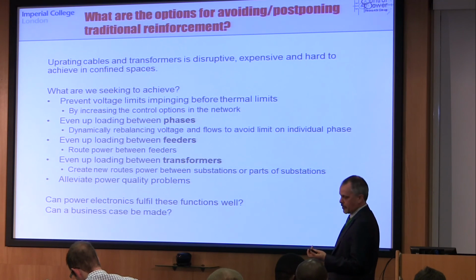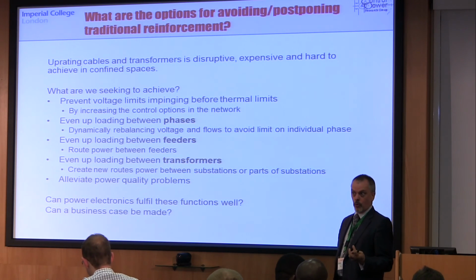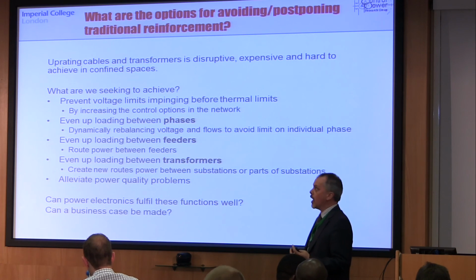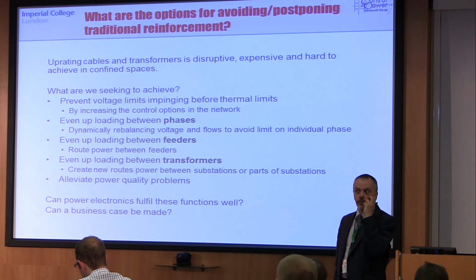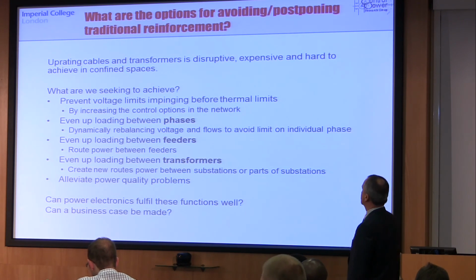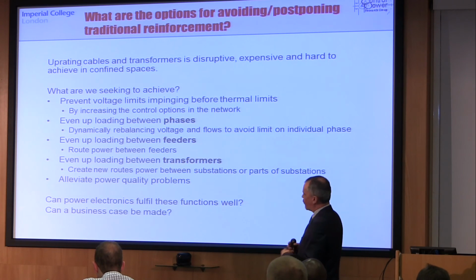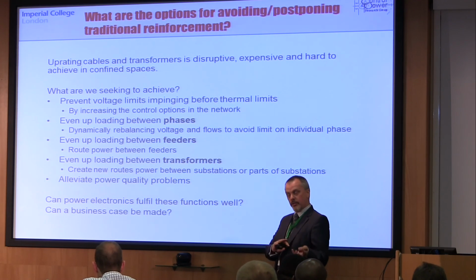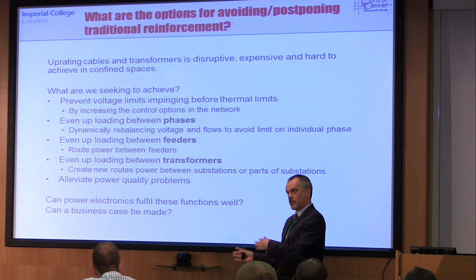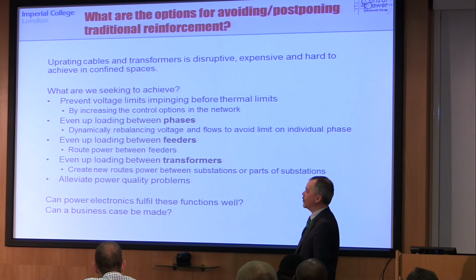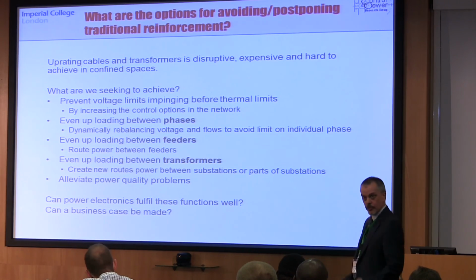As I already illustrated, often one phase limits before the other two, and that's something we can tackle with phase rebalancing systems. We also have problems with certain feeders limiting before others - plenty of capacity in the transformer, but not out on the feeders, because one feeder limits first. Can we do some feeder-to-feeder balancing?